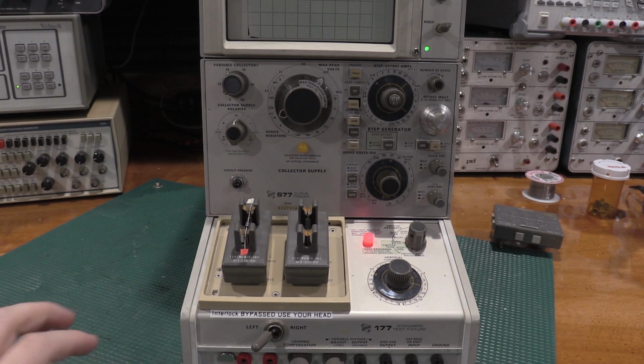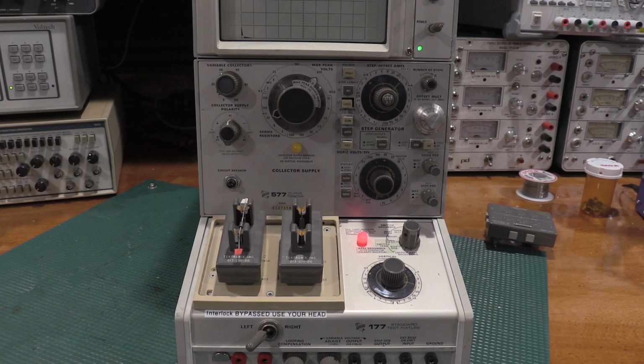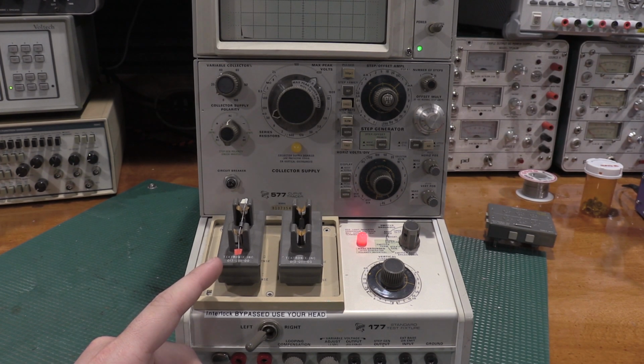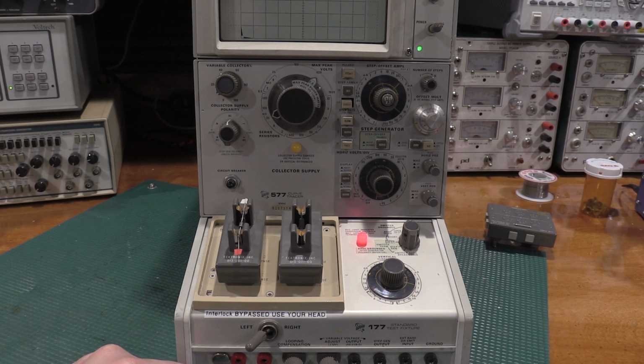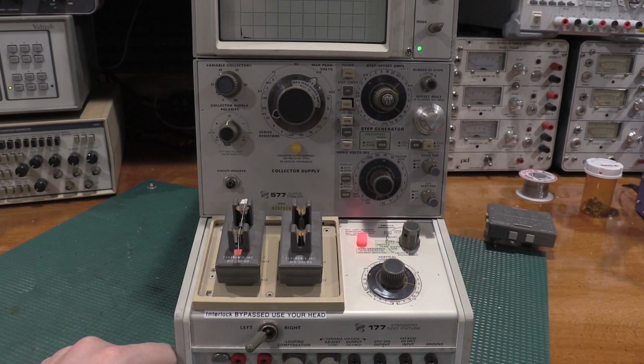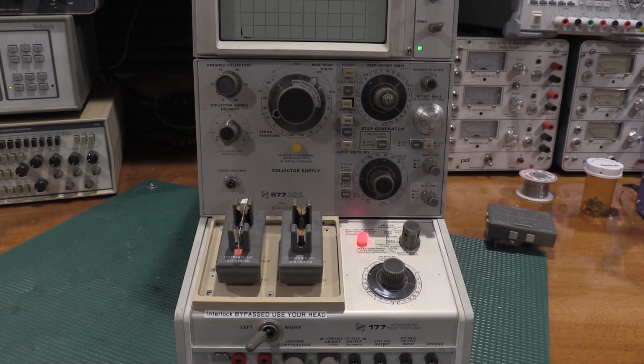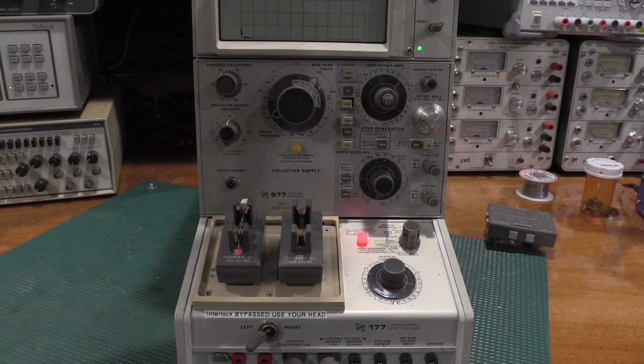I did find some of the parts from the 5200A repair that we can test out on this, and I can show you guys why I needed one. In this case, I have a 140 volt Zener diode, which was one of the main culprits in the 5200 that blew up. This is a new one, so I can't test a 140 volt Zener with any of my meters. They don't go up that high. Actually, for diode testing, the best thing I've got is the DMM 6500, which will actually only go to 10 volts. So I can test the forward, but I can't test the Zener voltage, which is what we need.